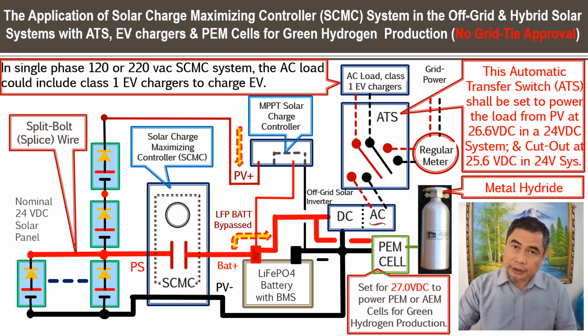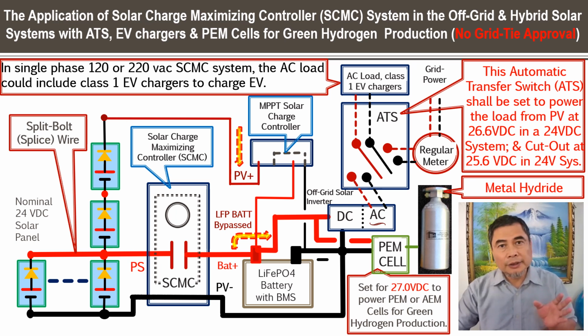This is another application, pretty much identical to what we just explained. It could be a 120 volt 60 hertz system or 220 volt 50 hertz system, single phase. But because you don't have that much AC load during the day, when you have maximum solar condition, you expect to have a lot of capacity coming into the system, but you don't have enough AC load during the day because it's not a grid-tied system. You cannot inject power to the grid. So it's a regular meter here only. You don't have the grid-tied approval, and you have a lot of this DC current going into the system, and then you may not have that much AC load to spend the power.